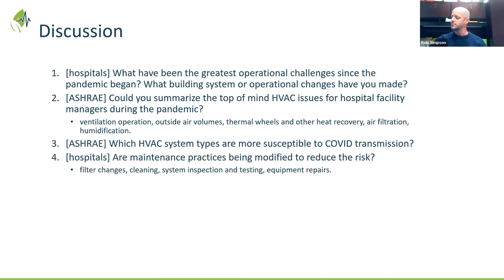Okay, interesting. So one thing you should be looking at in most of your units is making sure your filter gaskets and filters are sitting properly, because it doesn't matter how good your filter is if you have a bunch of air bypassing it, that could potentially be an issue.